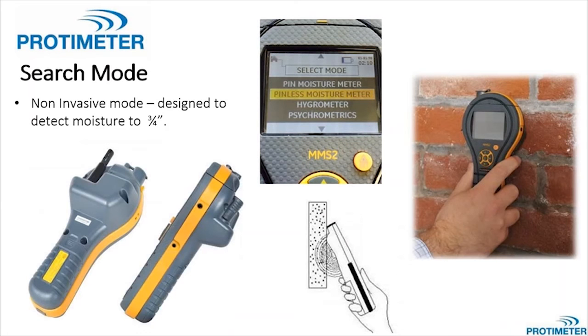The next mode and the next feature on the user screen is our pinless mode of measurement. It's based on radio frequency, and that radio frequency sensor will penetrate up to 3/4 of an inch into the material you may be testing. It's a nice feature, and just before this webinar I took a picture of the meter on my desk to give you an idea of the fact that this particular mode of measurement is unaffected by surface moisture.